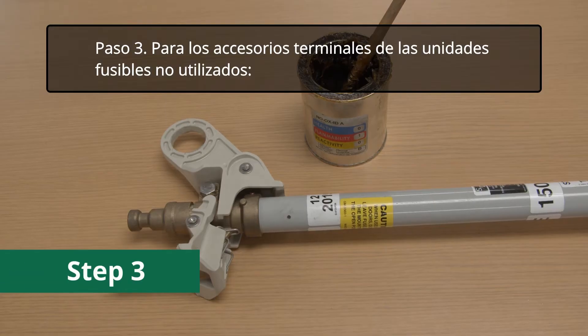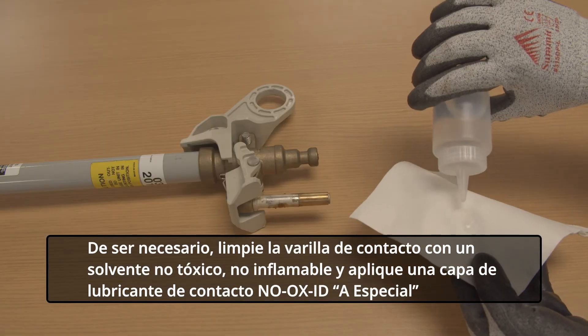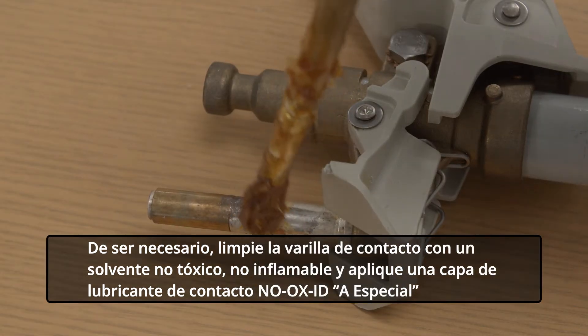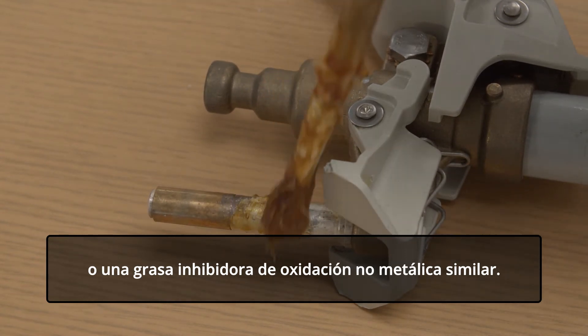Step 3. For unused fuse unit end fittings, a coating of No Oxide A Special oxidation inhibiting grease has been factory applied to the contact rod. Verify the presence of this grease and that it is still free of contaminants. If necessary, clean the contact rod with a non-toxic, non-flammable solvent and apply a coating of No Oxide A Special contact lubricant or similar non-metallic filled oxidation inhibiting grease.